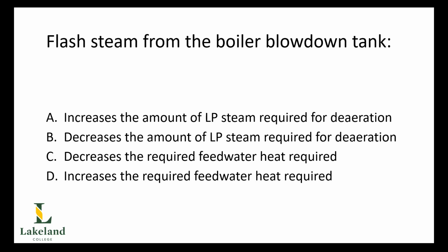Next one. Flash steam from the boiler blowdown tank, does that increase the amount of low pressure steam required for deaeration, decrease the amount of low pressure steam required for deaeration, decrease the required feed water heat required, or increase the heat required? Well, same as what we just talked about. If you look at figure 2, check out where our flash steam and makeup steam are entering into the deaerator. The more flash steam we put into the side of the deaerator, the less makeup steam we're going to require. So the answer here is going to be B. It will decrease the amount of low pressure steam required for our deaerator.